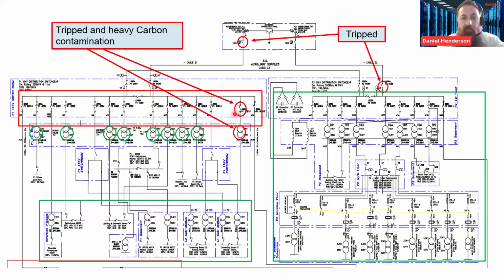So I suppose as part of a process then from this point, I've got additional support in place, and I've worked through the network, testing through various switching, safe systems of work processes, issue of safety documents, testing, visual inspections, and then I've started restoring. So I've restored this side of site first to get supplies back and get the light and small power on from a welfare perspective. And then on this side, because I know this is the area of the fault, I've taken a bit more of a measured approach. Again, a circuit at a time, testing, inspecting, and then restoring one at a time, leaving this circuit here isolated. And I've got everything on in around 6 hours.